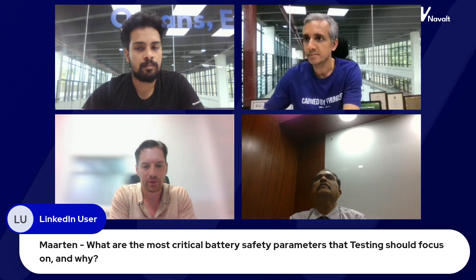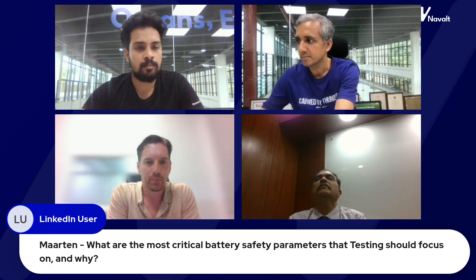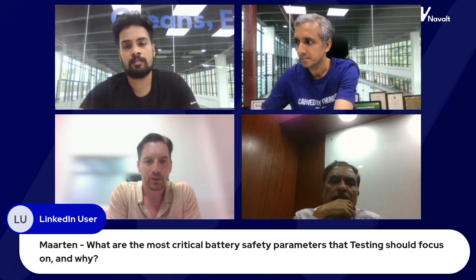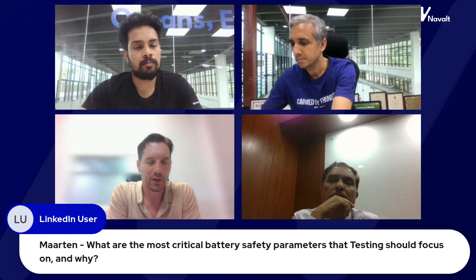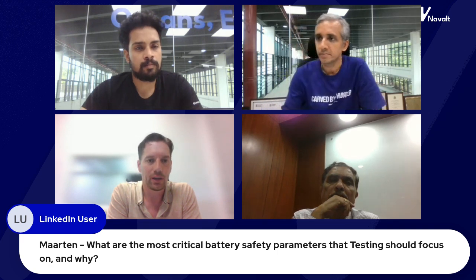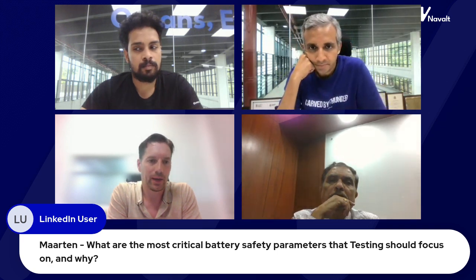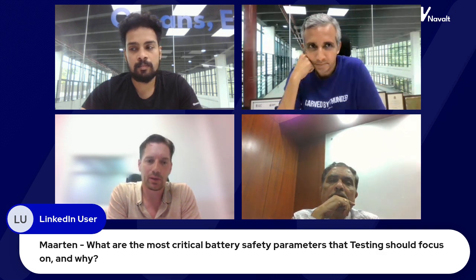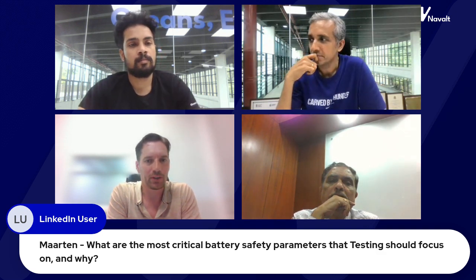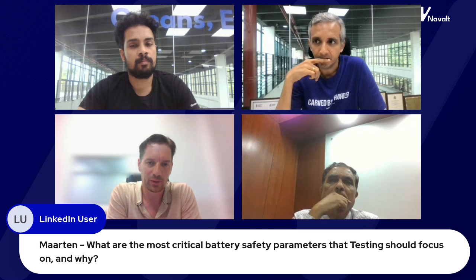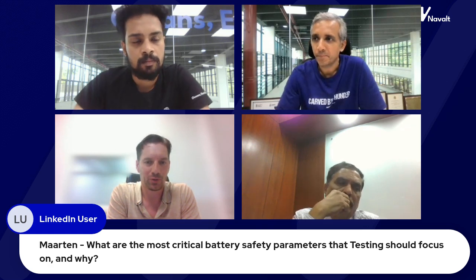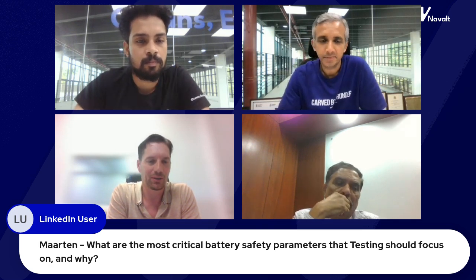So it's very critical to look at your components, what are the specifications of each one, and whether I'm using and applying it correctly, not misusing the component. It can be as simple as a contactor — some of them have a plus and a minus. It's a switch, but there's a plus and a minus on it. You have to connect it in the right order, not reversed, to avoid problems like sticking relays.